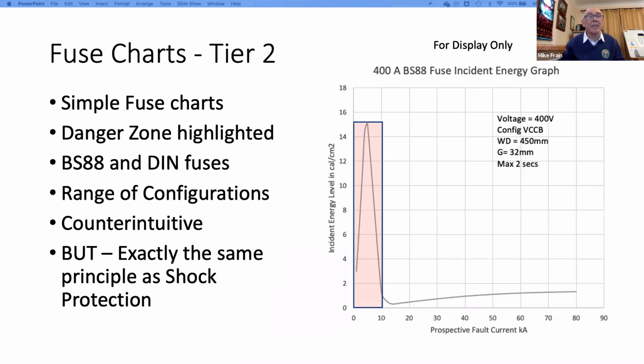So this is a tier 2 method that we put in, and these are simple fuse charts. And what this is, a 400 amp BS88 fuse. The DIN fuses are very similar, but there are separate DIN fuses as well. Predominantly, they are the IEC fuses that are in use across Europe. And I understand that the BS88 standard is starting to be used in the US, by the way. Somebody might put me right on that one, but I understand that the fast-acting devices themselves are in use over there.